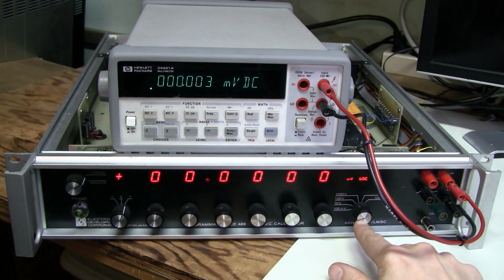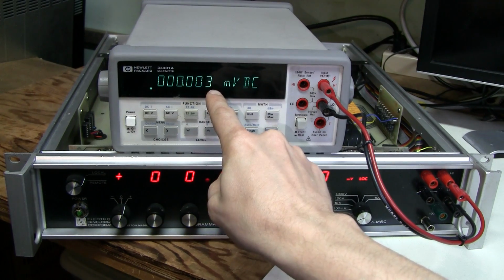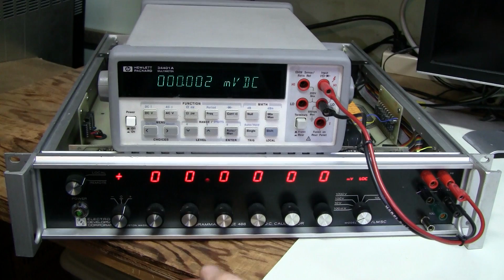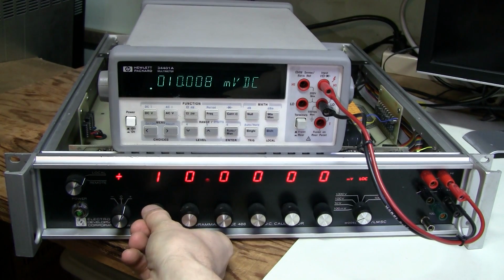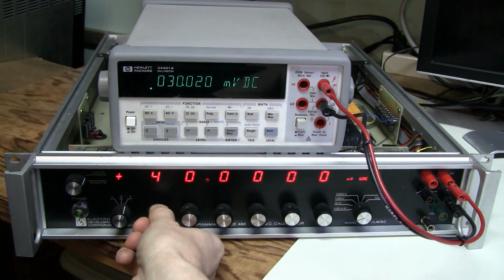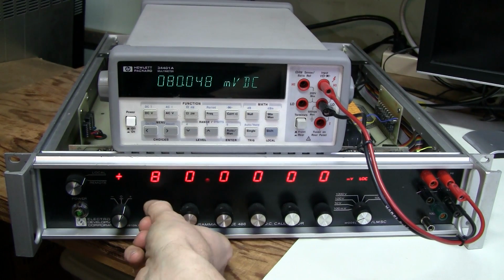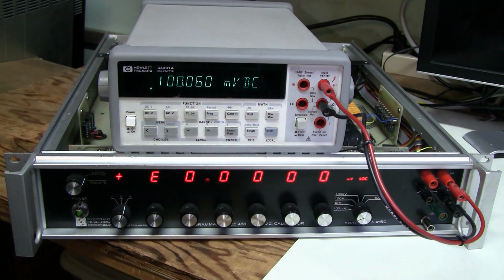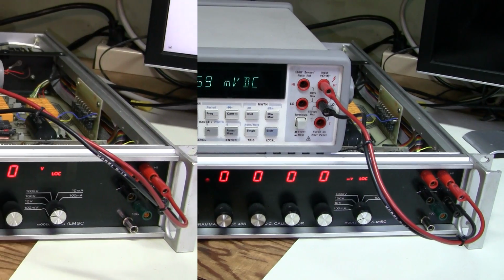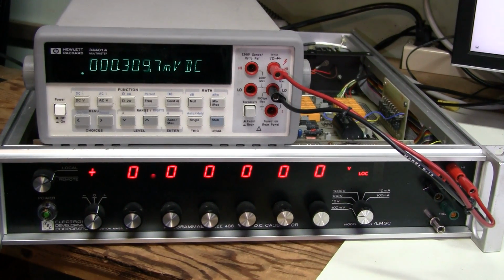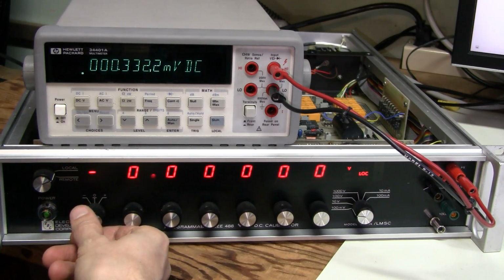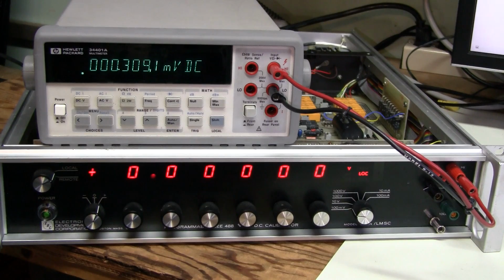And this is the 100 millivolt range, and the offset here is only 3 microvolts. 10 millivolts, 20, and so on. Works just fine. After warming up for several hours, the offset only increased to about 310 microvolts, and this offset does not change the polarity. And I think it means that the 0 point of the amplifier has to be adjusted.